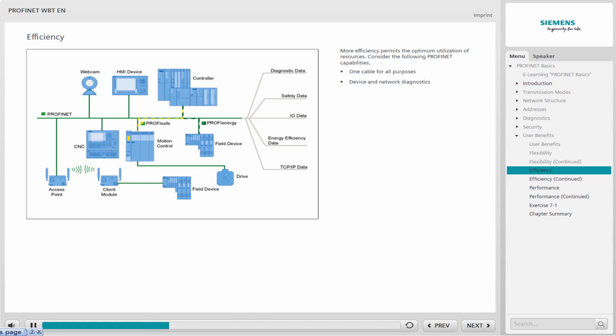PROFINET provides comprehensive device and network diagnostic capabilities. Easy and efficient access to the relevant device and network information during commissioning and servicing allows quick clearing of faults. Only a standard browser is needed for troubleshooting. Thus, service and maintenance can be carried out regardless of the location and engineering system.